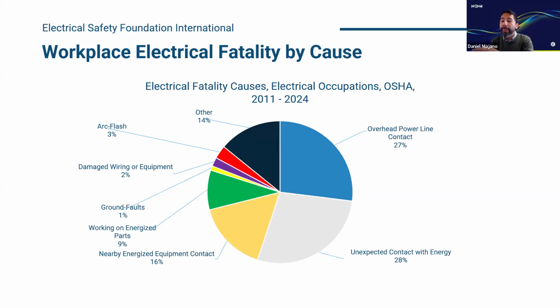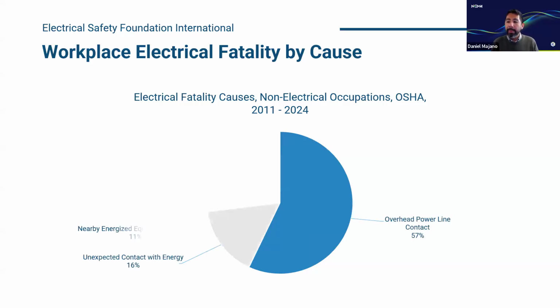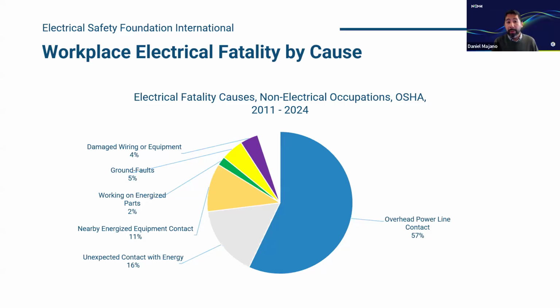If we look at non-electrical occupations, the numbers shift again. For non-electrical occupations, 57% of all workplace fatalities are caused by overhead power lines, so the majority of fatalities for non-electrical workers are caused by overhead power line contact. We're not seeing as much unexpected contact with energy, nearby energized equipment contact, working on energized parts, or arc flashes, but we are seeing more ground faults.